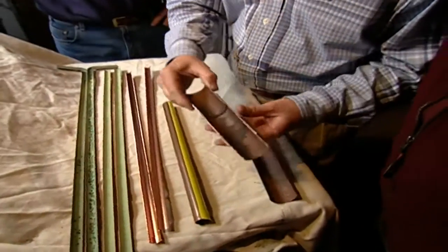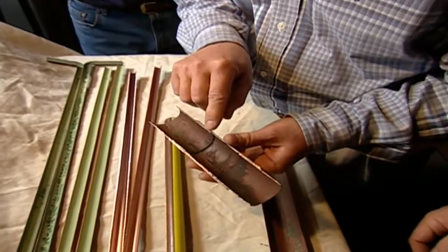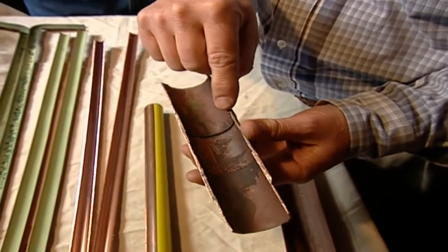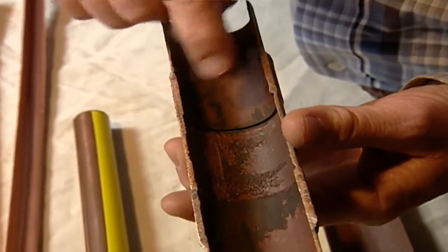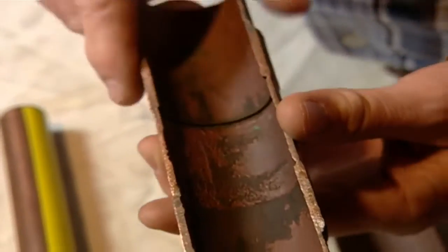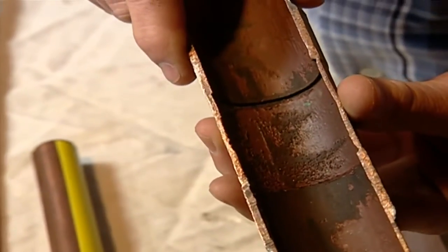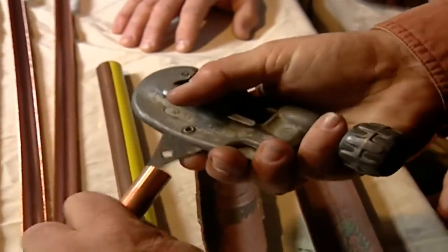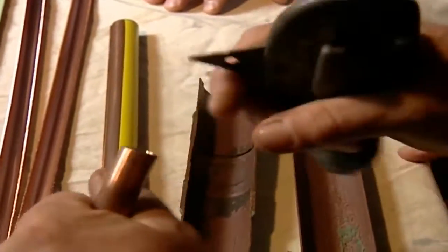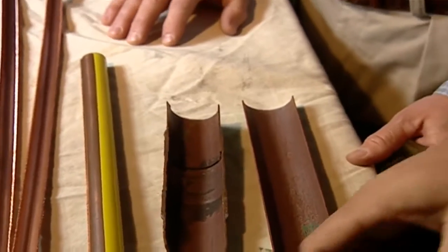Another related problem is where the ends of the pipe are not properly prepared in making solder joints. If the burr at the end of the pipe is not reamed to remove it, we have local turbulence, and that can cause another related erosion corrosion problem. That is so important. Most people have no idea that on every tubing cutter there's this, a reaming tool made to be able to open up that pipe so you won't get an impediment. That's right, very important. All right, what else?